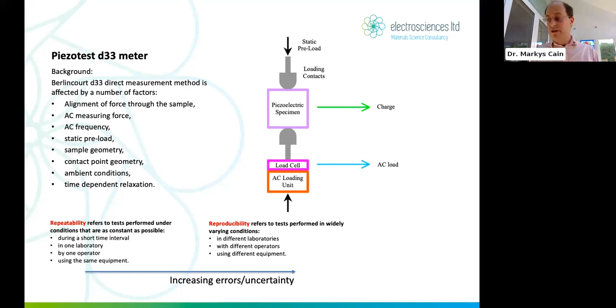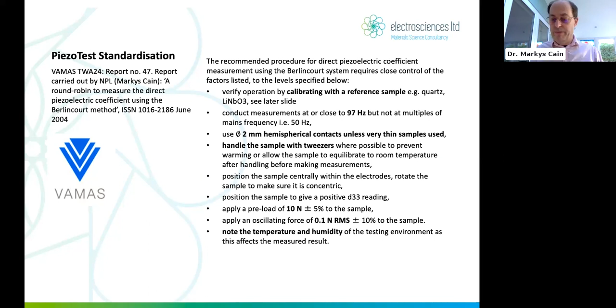It's this slide here. Now, back in, oh my God, 2004, so quite a long time ago, we started looking at this at NPL. And we came up with a recommended procedure for this direct piezoelectric coefficient measurement using this Berlin-Court system. And these were the recommendations that came through. And for the most part, these recommendations haven't changed. And we spent a lot of time doing this, of course. And we worked with a lot of different organizations. And some people on this call may have been involved in this famous round robin. I'm not sure who's on the call, but anyway, it's likely that some of you might recognize it. And we're going to go through this in the talk, okay? Reference standards, what frequency should we be using, what sort of contacts and so on. Why do we need to use tweezers to hold the sample? I mean, why do we need to position it centrally in the electrode? Why do we care? And so on. This is important stuff.